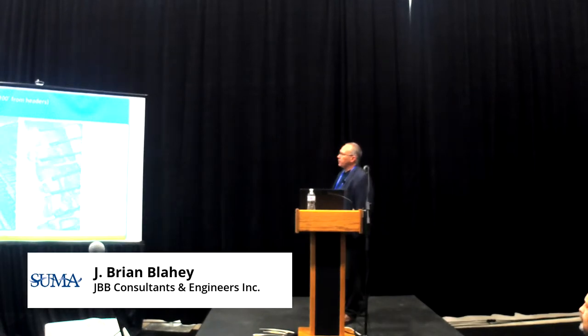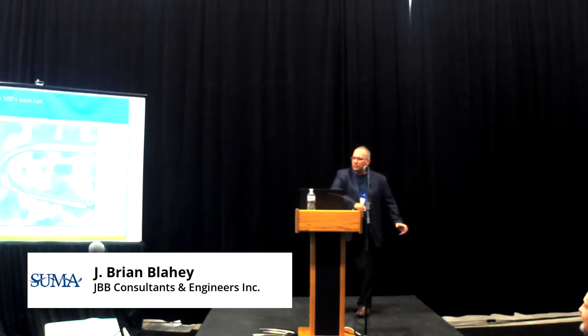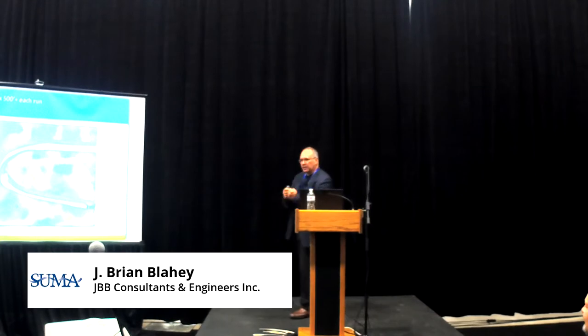There's the return bend trench on the other side. We just peeled back the plastic and came back, and we made a few mistakes. Having to turn that at 200 feet was quite difficult. We've got a couple of them shown here. They kinked, so we had to come up with a better way of turning that back. We did that 35 times.